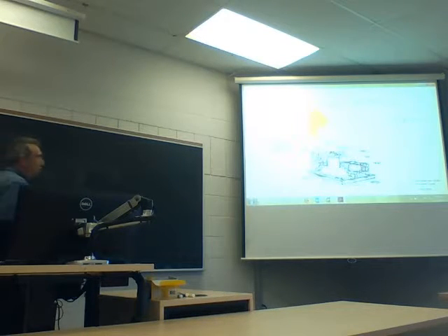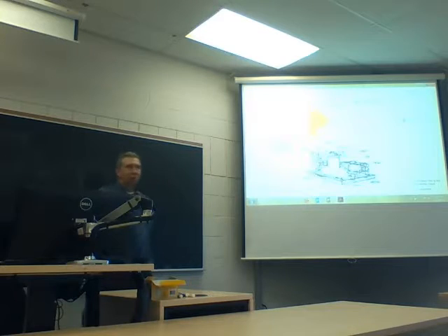Components. We're talking about a package unit here, so a package mounted industrial screw type compressor is what we're talking about. So we'll have a driver and intake filter, we can just look at it. Make note of the spiral valve there, okay? Just because we might talk about it when we're talking about control of the compressor. So basically it comes on a skid, you slide it in, and everything's there. The air dryers, the air filters, the oil separators, moisture separators, the cooler, everything is set there. All you gotta do is add hydro and water and you're good to go.